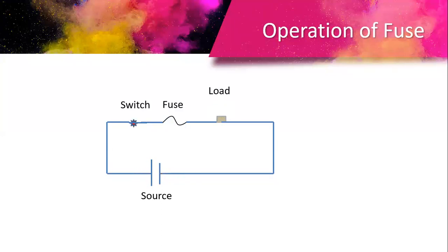You can see here, I am forcefully creating an earth fault, an LG fault, line to ground fault, in the circuit. Then whether the current continues flowing or stops, and what is the position of the bulb, you can understand easily. Now here I created the fault, the earth fault. Then what happened? When the fault current is very high, in the fuse you can see there is a spark. The spark is nothing but a high temperature, 3000 degrees centigrade. This temperature easily melts the fuse element and breaks the circuit. Then the current is stopped. It is not flowing in the circuit. You can observe this.